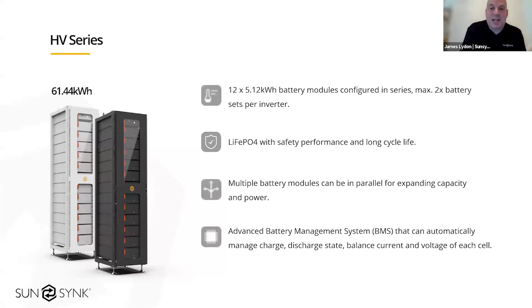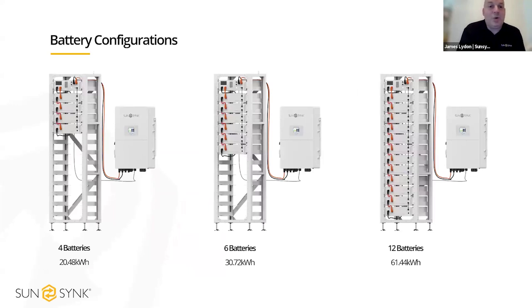On the slide, this shows you different configurations. The minimum amount of the individual 5.12 batteries connected to each HV inverter is 4. So the end user could start with, let's say, 4 batteries in a stack to see how they get on, monitor the data, and if they wanted to, they can add more individual modules. This is something that Segen are going to be doing directly, or they can purchase it at the full 12 modules, which is 61.4 kilowatt hours of storage.